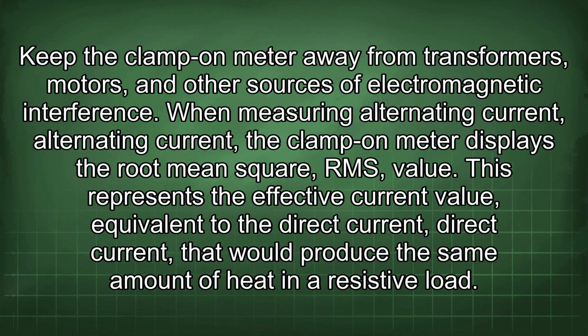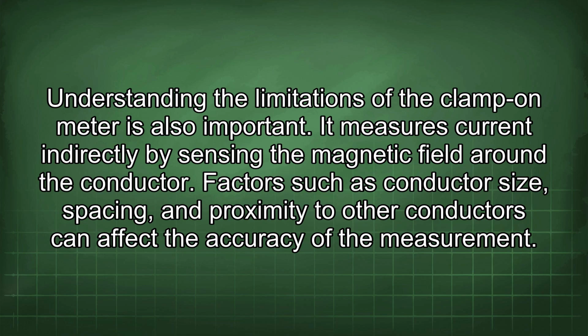When measuring alternating current, the clamp-on meter displays the root mean square (RMS) value. This represents the effective current value equivalent to the direct current that would produce the same amount of heat in a resistive load. Understanding the limitations of the clamp-on meter is also important. It measures current indirectly by sensing the magnetic field around the conductor. Factors such as conductor size, spacing, and proximity to other conductors can affect the accuracy of the measurement.